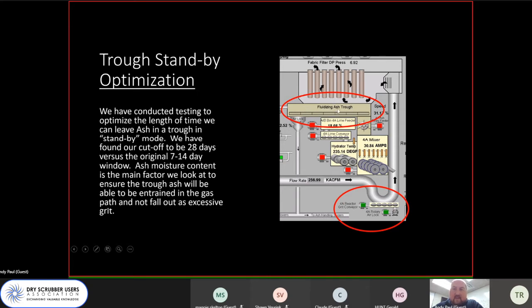If we leave this ash in here too long, just for everybody's understanding, we're going to get a lot of solids and heavies, and we're going to overwhelm our grit conveyor down below. That causes a lot of operational headaches trying to remove that material from the J-duct efficiently. So it's a fine line to walk, but we think we found a pretty good cutoff at that 28-day mark. There's a little seasonality to it, but we've tested across the board, and that's where we came up with 28 days. We probably could get 30 at certain times of year, but 28 is an easy number to remember, and it fits nicely with most of our outage lengths.